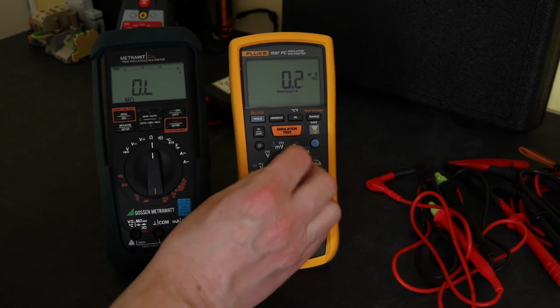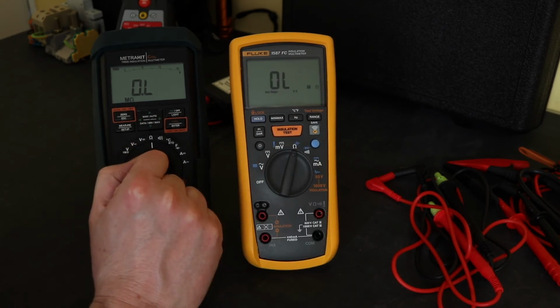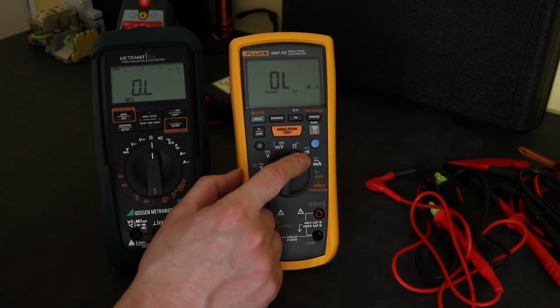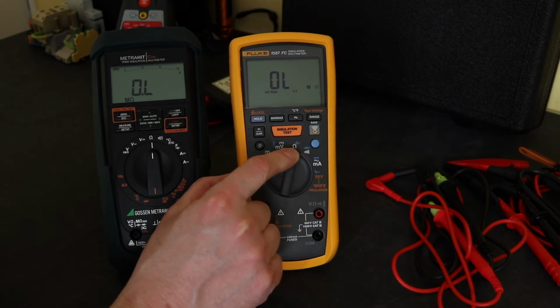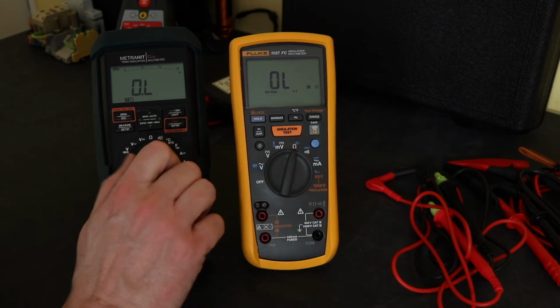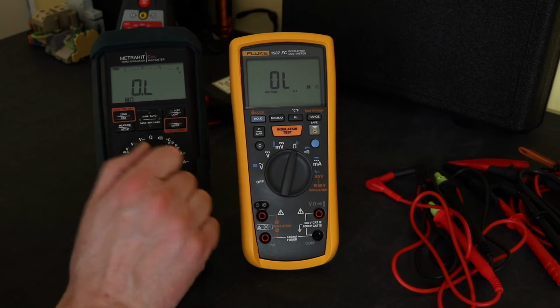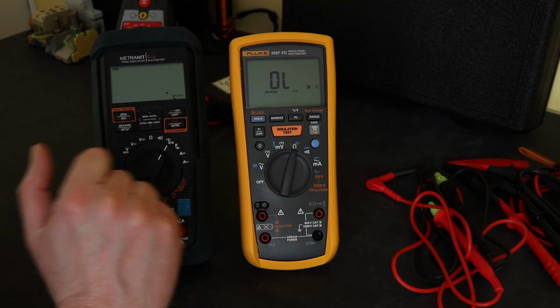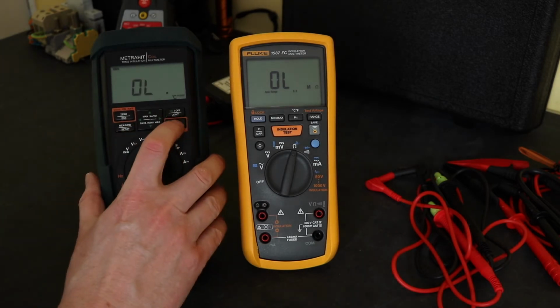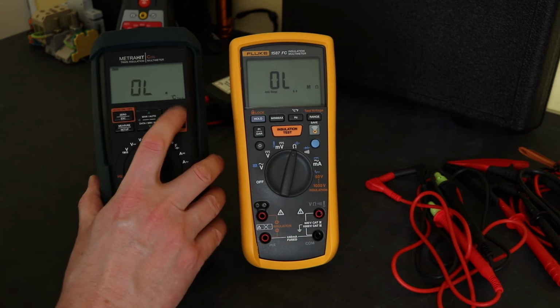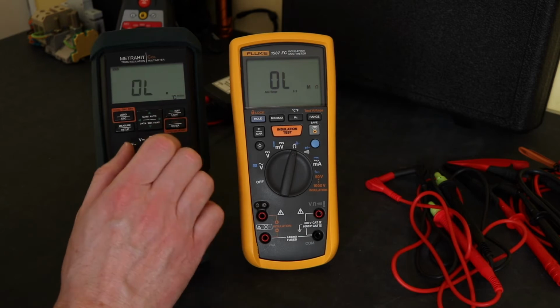Next one round is ohms. You have ohms on there as well. On here you have capacitance for this function, and this is a separate function actually mixed in with the temperature that was over here on the millivolts. To flip between the two, you just use the function button here, and it can tell you it can do a type K or a PT 100.